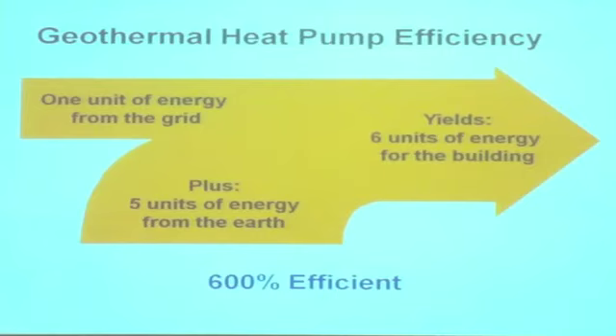So roughly, in heating mode, you're looking at 600% efficient. You buy 1 unit off the grid, the electricity to run the compressor and fan. You pull 5 units of heat out of the earth, and that yields 6 units of heat in the building. So let's look at it in dollars. You're buying $1 off the grid to run the compressor and fan. You're pulling $5 out of the soil through that red and blue line, and you're putting $6 into the house as heat.